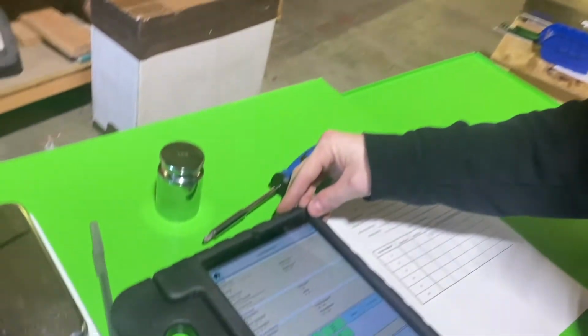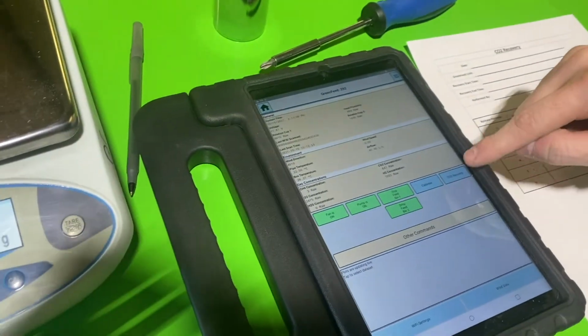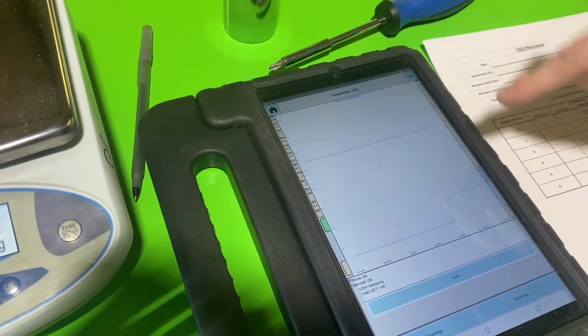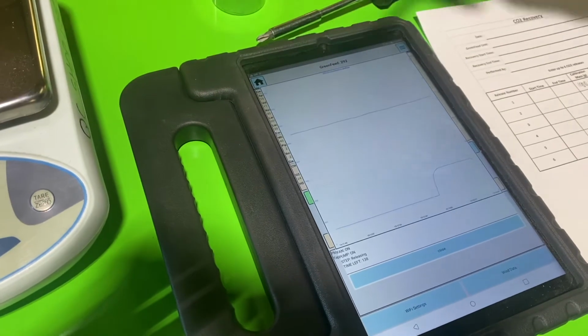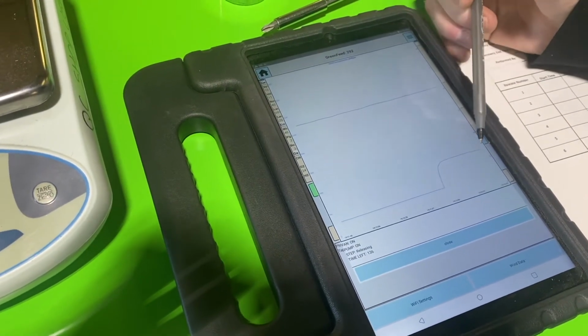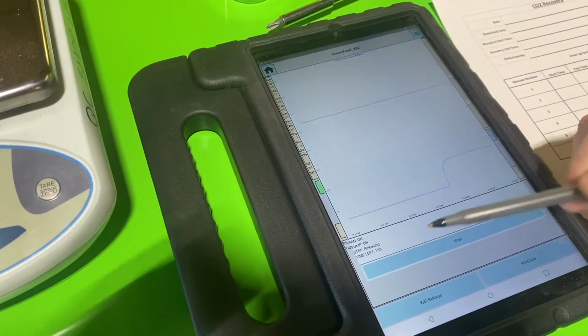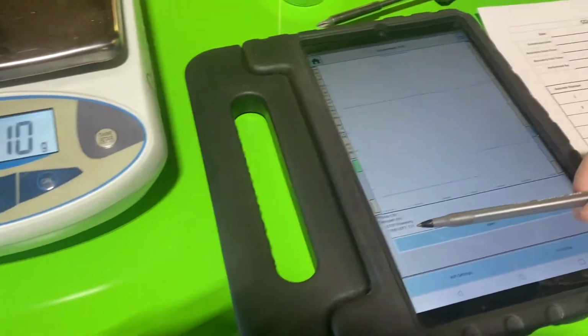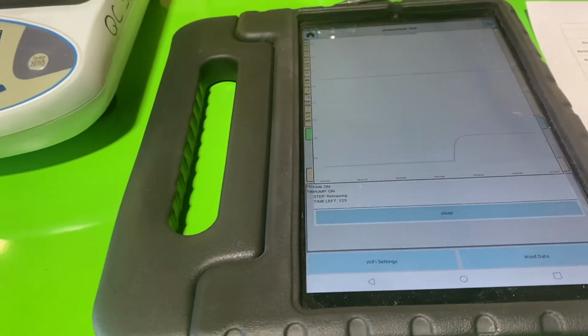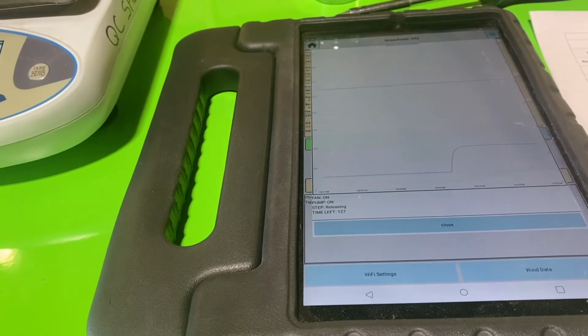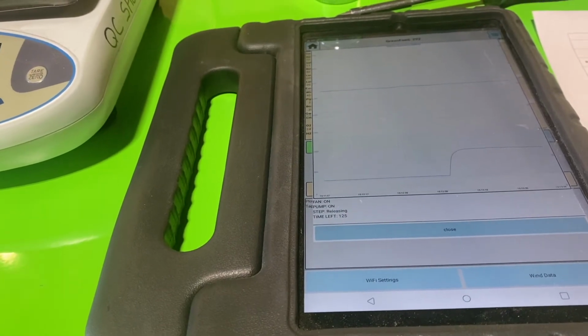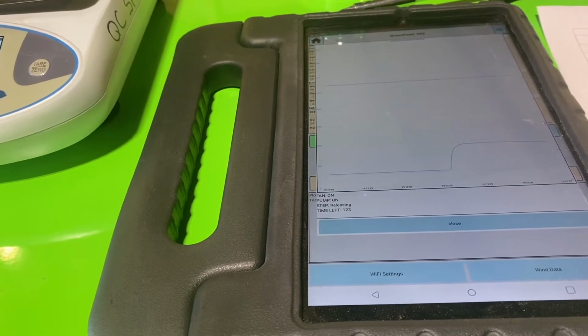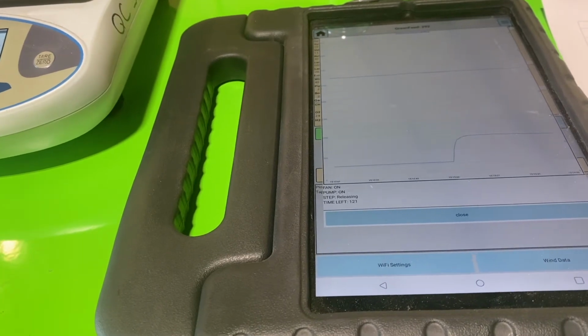What we want to do is release for about 3 minutes. If you have the control feed app open, we can press on this CO2 Recovery button, and we can actually see the CO2 being released into the system right here. It's also going to keep track of how much time we have left on a release. So we have 130 seconds left on the release. But we may go longer for subsequent releases, depending on how much we're releasing during this first one.